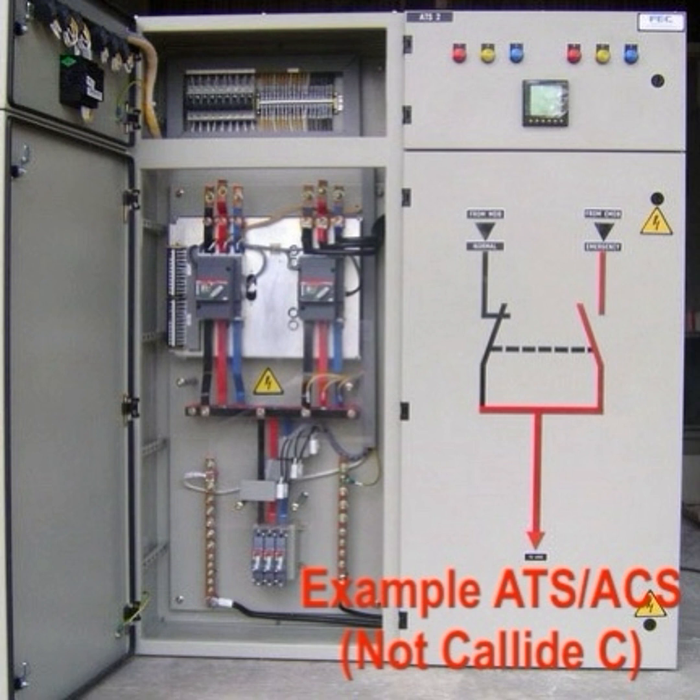The other point of note here is that the DC bus design intentionally interlocks against closing two battery banks in parallel at the same time. I've watched electrical engineers like me early in my career state that the risks are overblown and there's nothing wrong with doing that, to, in more recent years, people being terrified of paralleling battery strings at all. Why it can be a problem relates primarily to imbalance between the battery banks. All batteries have an internal resistance that changes based on their charge level and battery health, let's say.